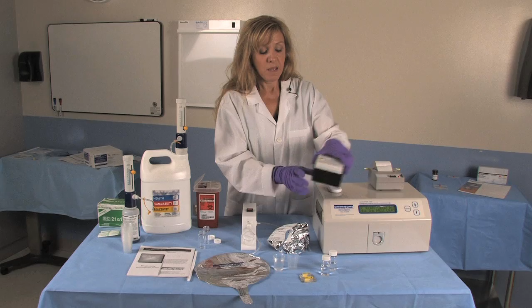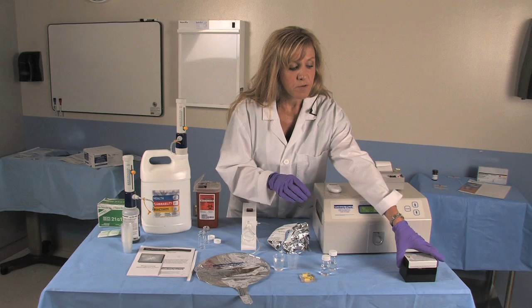The standard sets that were typically provided with the microcount lights have 20,000 DPM. The new standards can vary in the amount of DPM. So an adjustment must be made to the machine to allow for a different value of DPM. For machines purchased after November 2009, the machine windows have already been adjusted for variable amounts of DPM. Once the potentiometer has been changed so that the window is open, the owner's manual for the microcount light needs to be consulted. Page 9 and 10 of the owner's manual instruct you how to change the default setting for the DPM from 20,000 to the value on the new standard set.